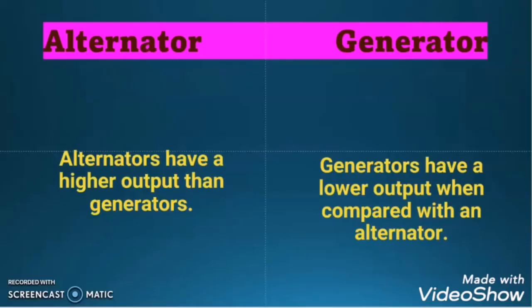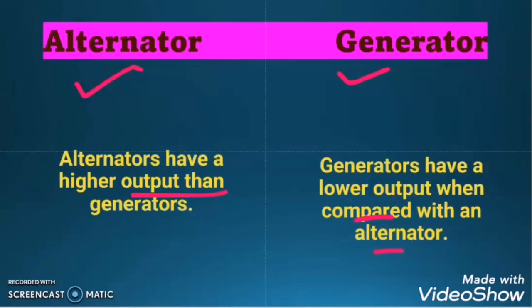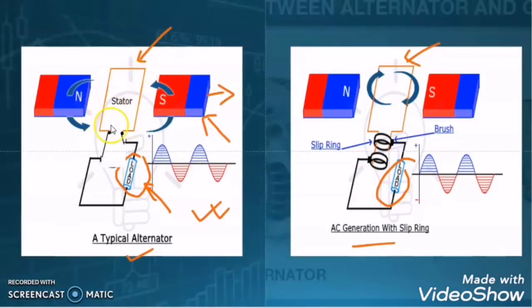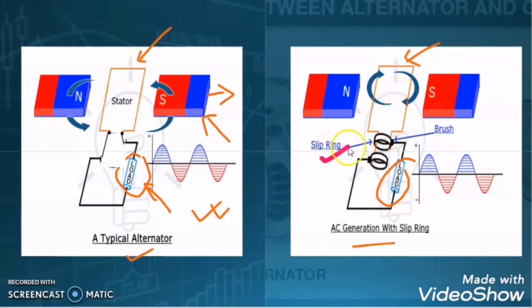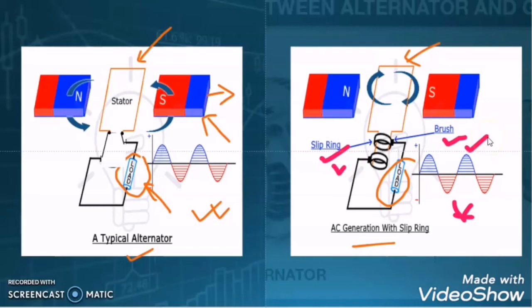Another difference between alternator and generator is that the output of the alternator is greater than that of the generator — the generator's output is comparatively less. The reason is that in case of an alternator we are getting the power supply through the armature which is stationary, so we do not require any carbon brush and slip ring arrangement. But in case of a generator, we are getting power supply through the armature which is rotating, so we need a slip ring and carbon brush arrangement, which reduces the output of the generator. In electrical engineering, wherever you use the slip ring and carbon brush arrangement, you are compromising with the output, decreasing the efficiency, and increasing the maintenance.